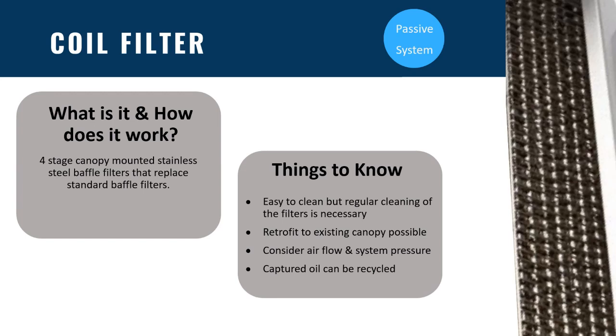There are 4 stages to the operation for coil filters. Firstly, the oil vapours condense on the large surface area of the filter coils as heat is transferred from the air. The air is then spun into a vortex and the droplets of oil and grease continue in a straight line. These particles then collide with the filter coils and the oil-coated filter surface traps more oil and grease due to its enhanced viscosity. The oil and grease droplets simply settle due to gravity and then are collected for recycling.